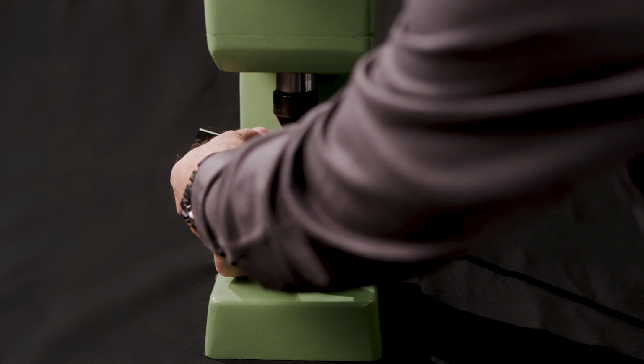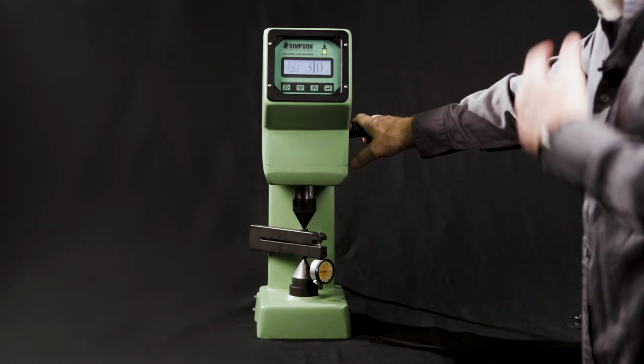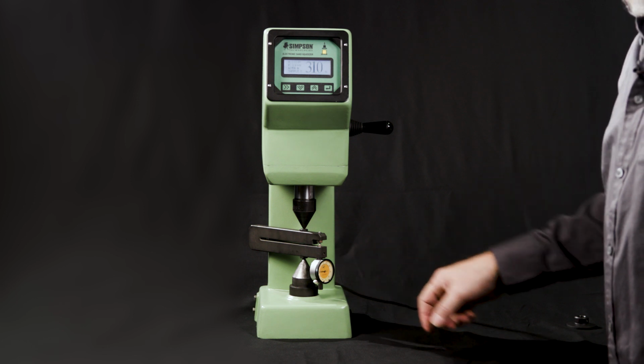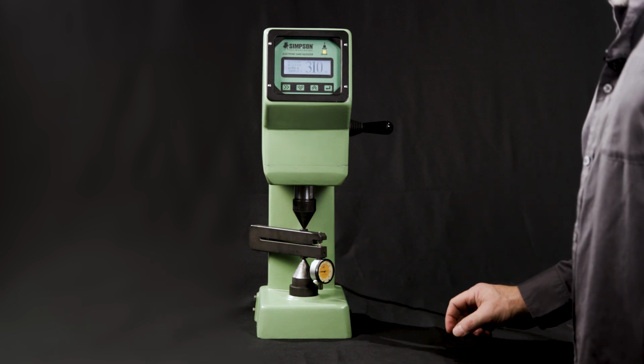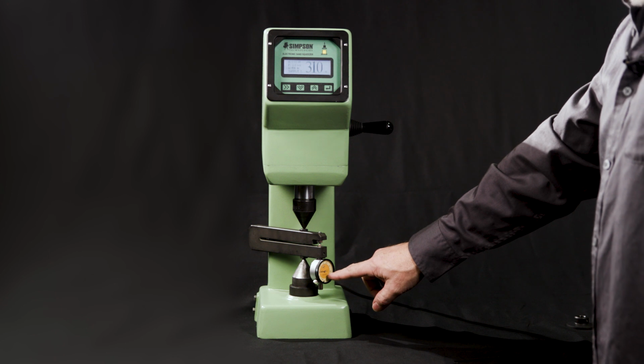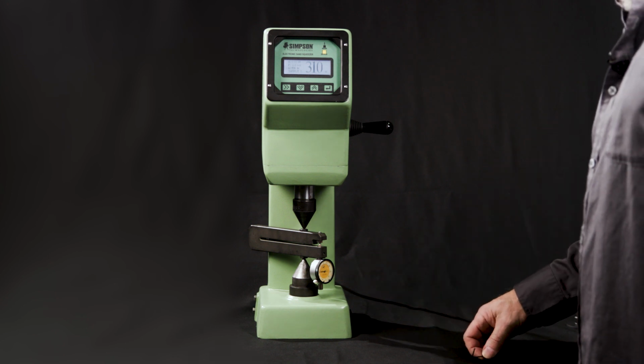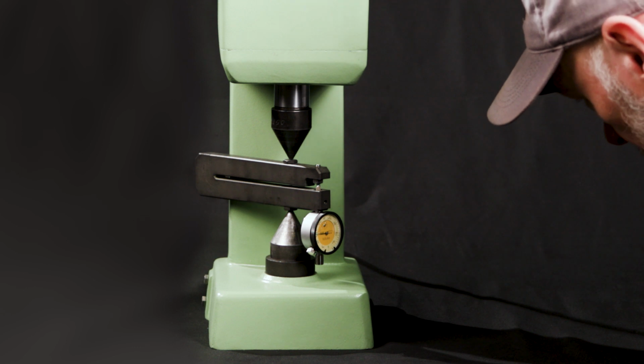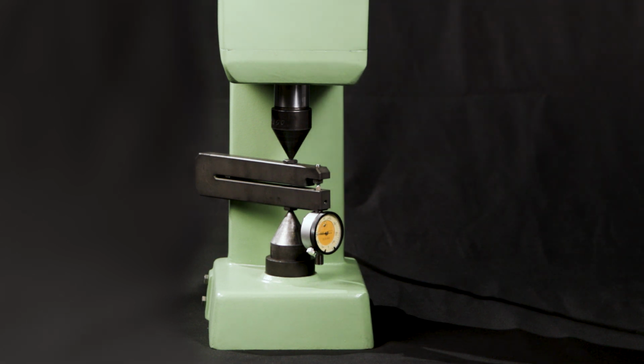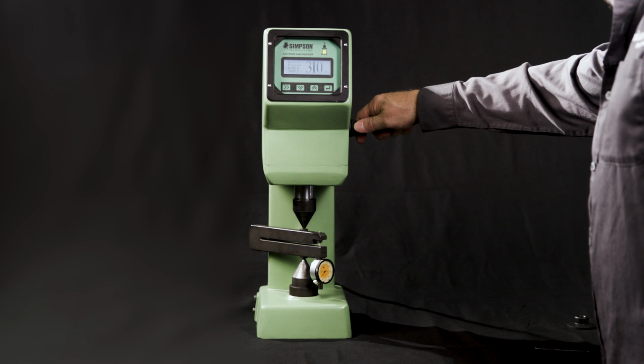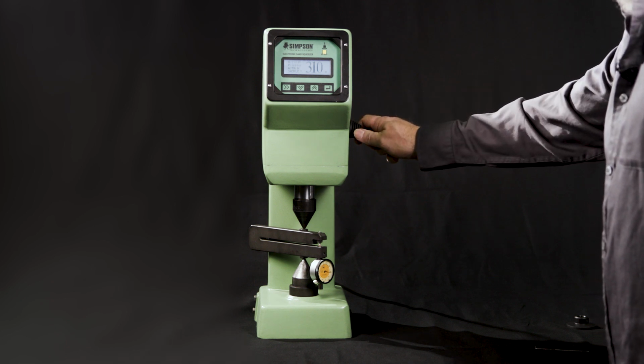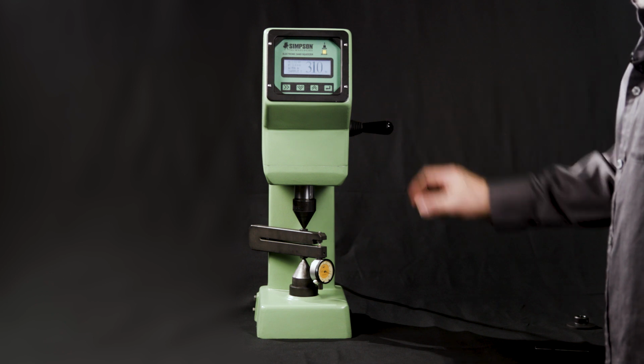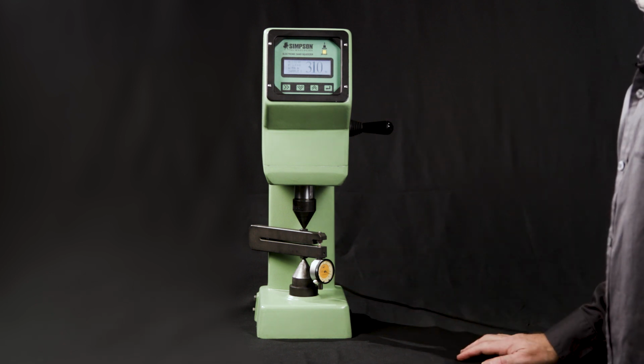Then we are going to set our mechanical load cell on the equipment here, and we are going to descend the piston to apply pressure to this manometer. At this point, we are going to set the air pressure for a specific amount of pressure on the mechanical load cell. At the moment, we are looking at decreasing it slightly. We are over the range by about 40 millimeters of deflection. So I'm going to release some of the pressure on this, and then I'm going to put pressure back onto it. At this point, we're looking to get 145 millimeters of deflection on the mechanical load cell. We are at about 142.